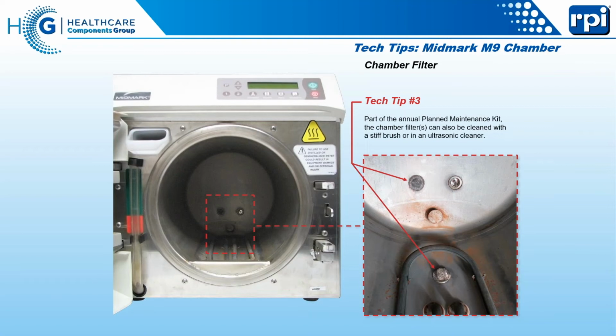As you can see, this is a nice clean chamber wall. This is the water level sensor. We want to make sure this area stays clean because it needs to be conductive between this metal plate and the wall of the chamber. So we want to get off all lime scale and calcium buildup on there. Also, this is a view of our temperature probe, and it has a metal bar sticking into the chamber, and you want that to be clean. You don't want any scale built up on that where it might insulate it and change the temperature that the machine thinks it's seeing.